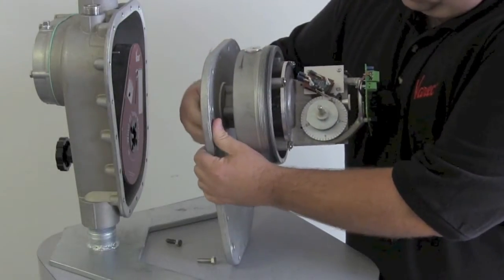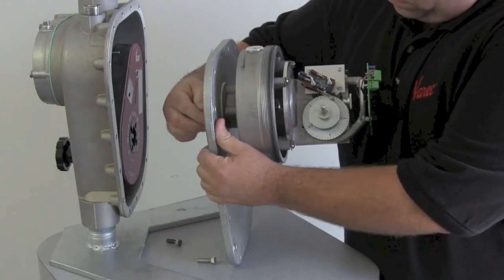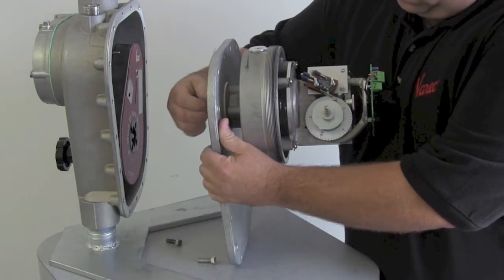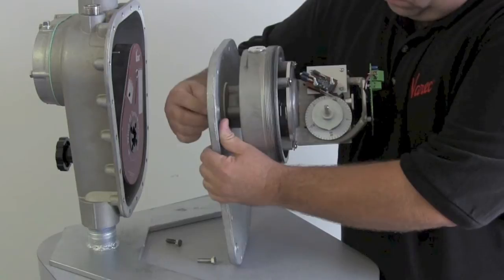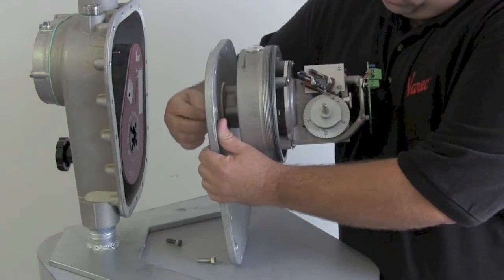Now to calibrate it, turn the coupling so that the transmitter's dial, the one inside the transmitter body, reads zero. It is worth noting each turn is one foot.